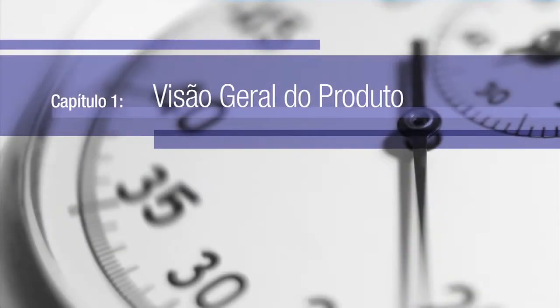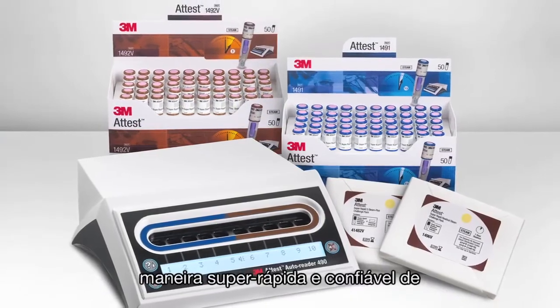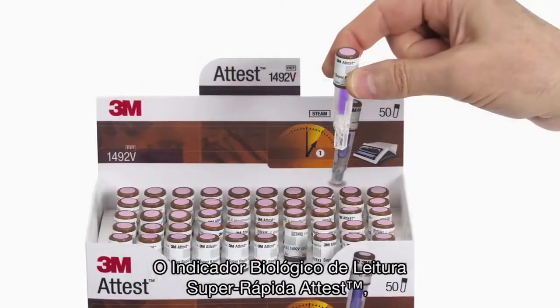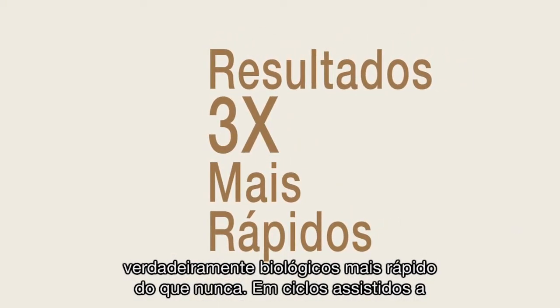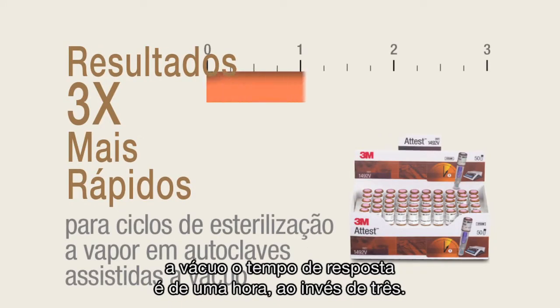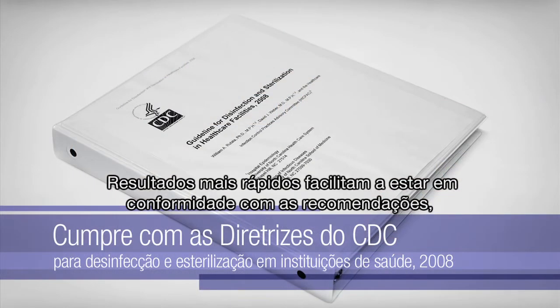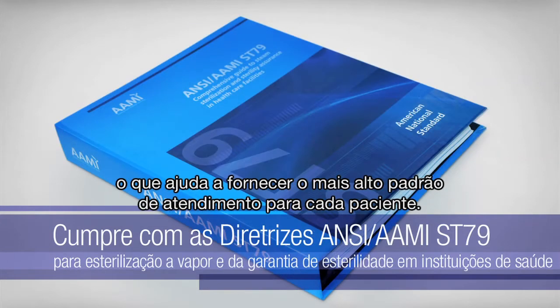The 3M Attest Super Rapid Readout Biological Indicator System is a super-fast, reliable way to monitor steam sterilization processes in healthcare facilities. Attest Super Rapid Biological Indicators, or BIs, dramatically decrease turnaround time by providing true biological results faster than ever before. 270°F vacuum-assisted BI incubation time is just one hour instead of three. Faster turnarounds make it easier to comply with sterilization guidelines, which helps you provide the highest standard of care for every patient.